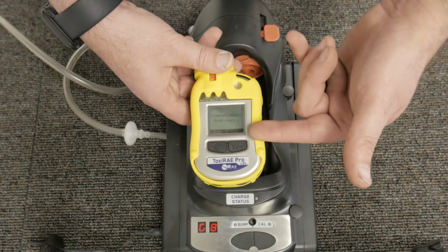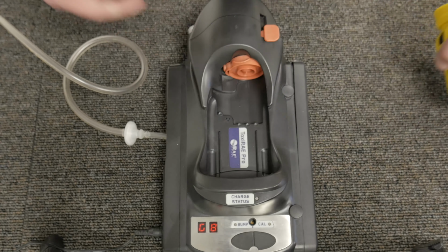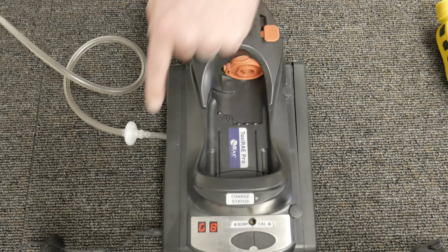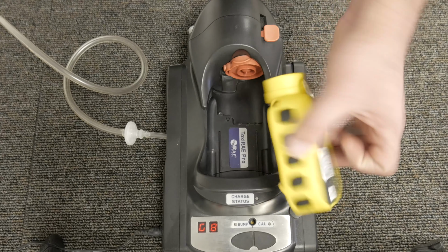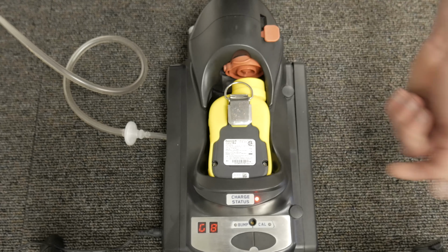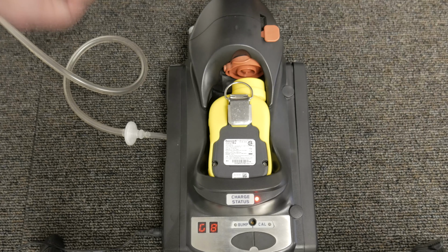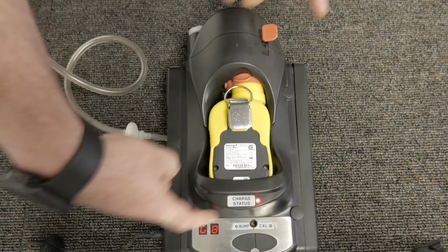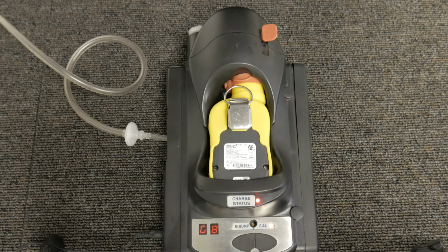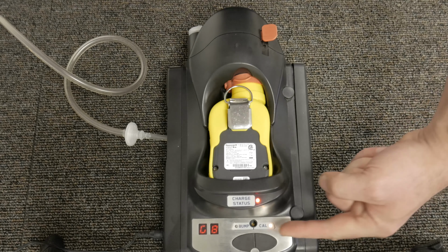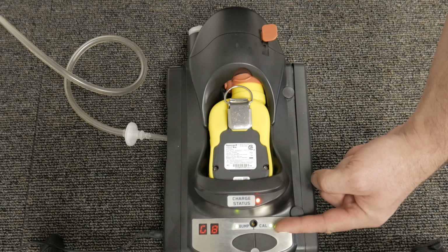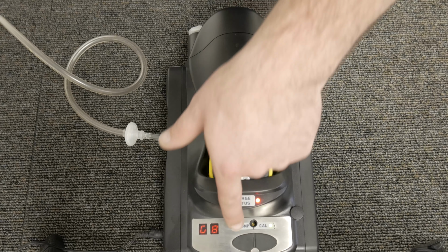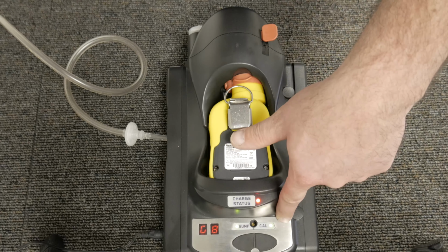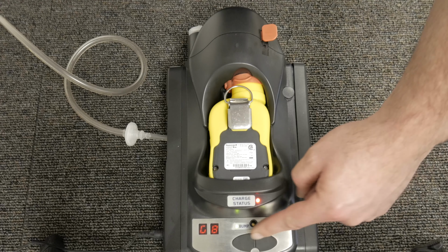Now grab your ToxiRAE Pro in the communication ready mode. Once again, before you seat it into the unit, make sure everything is hooked up and properly working. Turn it upside down, and as you see, the red light turns on. That means it's charging. And then you just snap down the hammer. And you will also notice that the bump and cal buttons are illuminating. And then once it's communicated, they both illuminate green. And then you can pick either the bump or the calibrate button, whichever one you want to use. For this option, we will use the calibrate button.